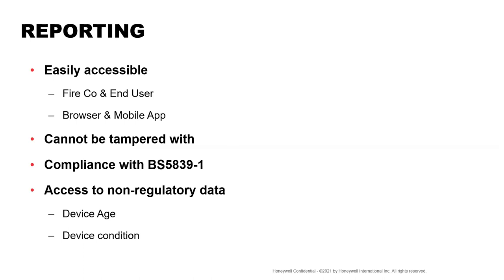So basically what we're saying is we can keep compliance of the certification and all the information that's on it, and we can make sure it's 100% accurate. Routine service and maintenance certificates, as well as any commissioning certificates, should be designed to mimic the paper versions that are currently available, which are all handed over. And they should obviously also comply directly with BS 5839 part one, which is the Bible to which we work. Both the end user and the service and maintenance company will have access to the device age and the device condition.